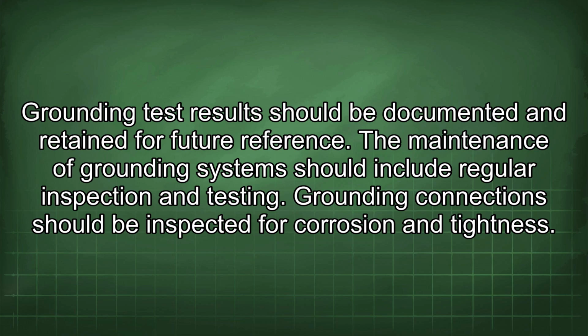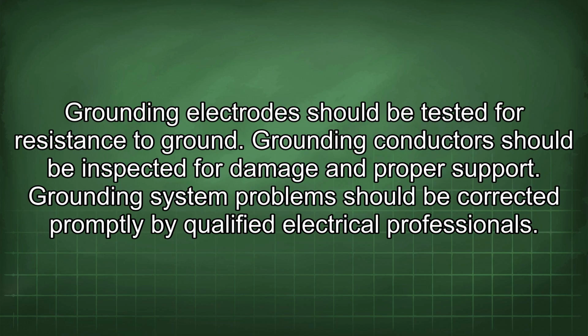The maintenance of grounding systems should include regular inspection and testing. Grounding connections should be inspected for corrosion and tightness. Grounding electrodes should be tested for resistance to ground. Grounding conductors should be inspected for damage and proper support. Grounding system problems should be corrected promptly by qualified electrical professionals.